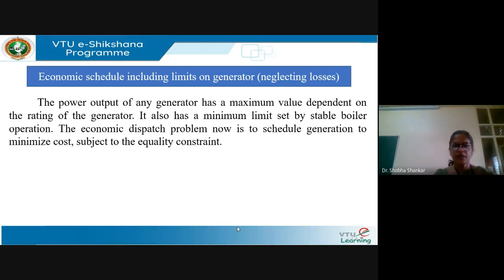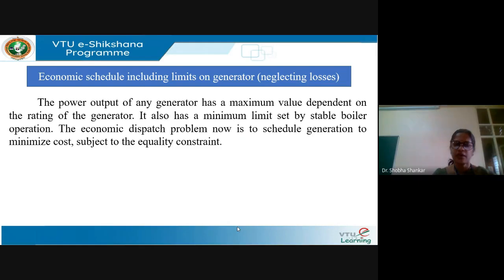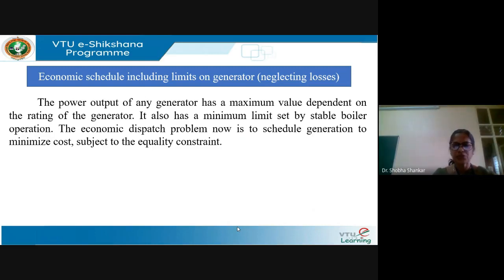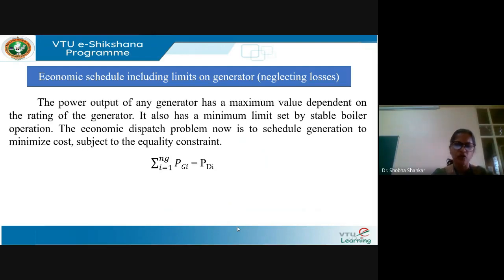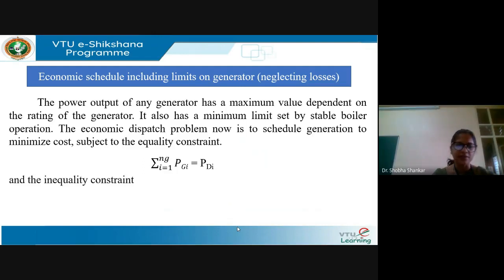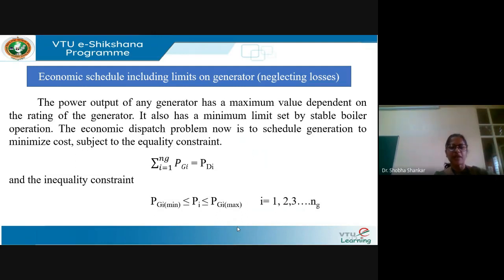The generators in the power system need to be operated within the minimum and maximum limit. The maximum limit is decided based on the rating of the generator, and the minimum limit is primarily based on the technical feasibility of operating that plant. The economic dispatch problem is to schedule the generation to minimize cost subject to the equality constraint: total generation equals total demand, with the objective function being minimization of total fuel cost. In addition, we also have the inequality constraint, that is the limits on the generator output.